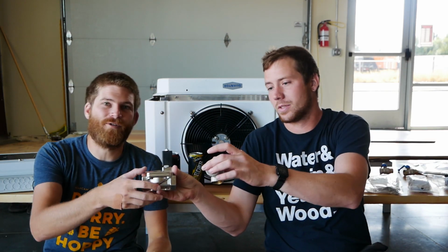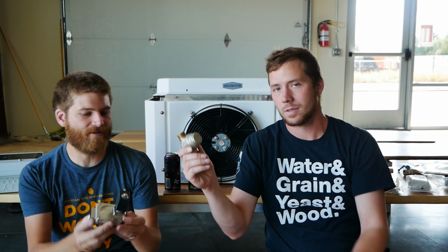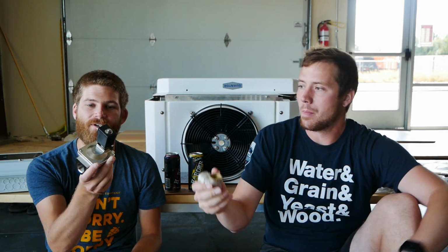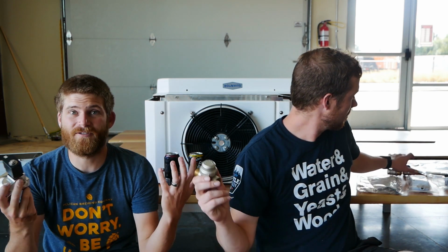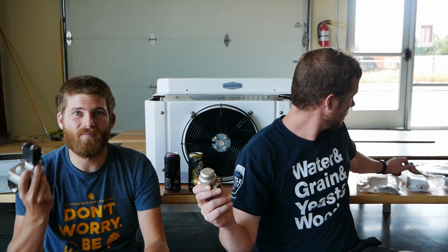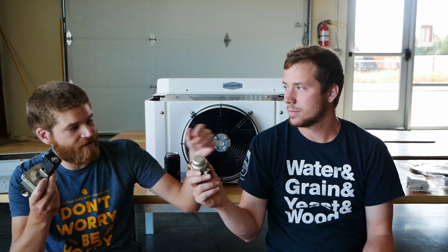Solenoid. So how the control filter box works is it controls this solenoid, which allows flow through or no flow through, essentially stopping the glycol from running. In order to achieve your temperature, this filter has to go in line with it because there's pretty small piping in there. If we get any debris in our glycol chiller, while the pump and lines can handle it, once it gets into that heat exchanger it has the potential to plug it up. So having some kind of inline filter is a really good idea.